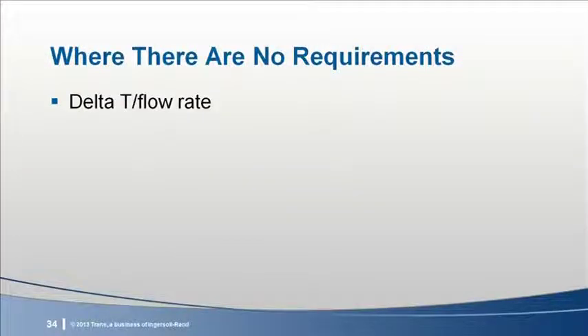The big problem with defining the code minimum chiller is that several design choices have no requirements. For example, the 90.1 prescriptive path does not have a requirement for a certain delta T or flow rate. Only the performance path defines these. The performance path budget for chilled water pumping is 22 watts per GPM for chilled water pumping and 19 watts per GPM for condenser water pumping. The prescriptive path is silent on delta T and how much water to pump. However, a 12-degree delta T, 44 to 56, is the baseline for calculating LEED performance and possible credits.